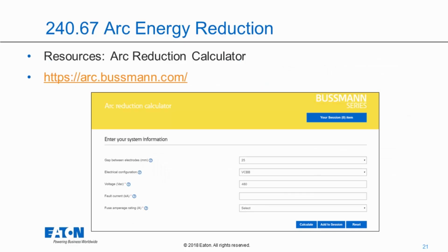So how do we make this easier for you? The last thing we want is for people who are not familiar with arcing current to try to calculate it. So we developed a program, and if you just type in arc.bussmann.com, you will find our arc reduction calculator. We also have an arcing current calculator, which is an older version of this. That version only did the calculation of the arcing current, and the equations used were for the old version of IEEE 1584. The reason you want to use this calculator is that it is based upon the revised equations in the 2018 edition of IEEE 1584, and it also does the analysis of the time current curve to see if you need additional technology.